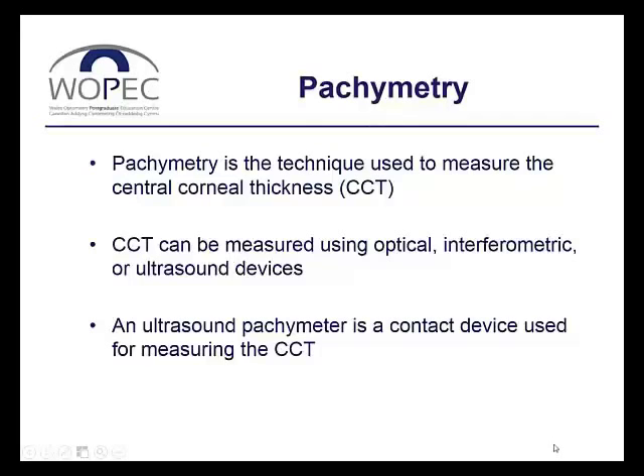The accuracy of all tonometric devices is affected by the biomechanical properties of the cornea. Pachymetry is the technique for measuring the central corneal thickness, or CCT, which can have an effect on the IOP measurement. The central corneal thickness can be measured by optical, interferometric, or ultrasound devices.